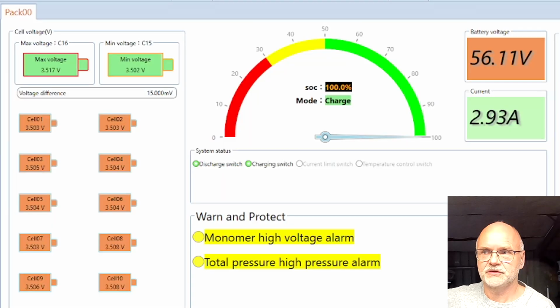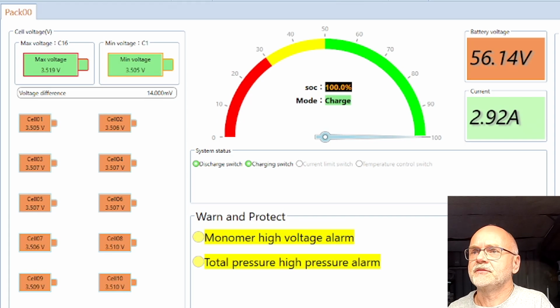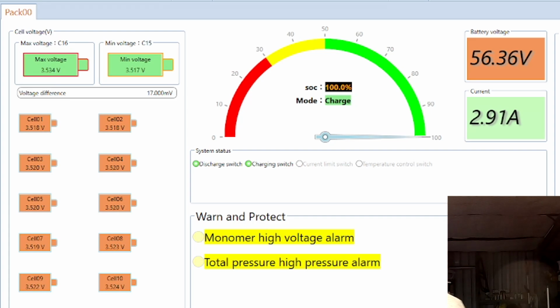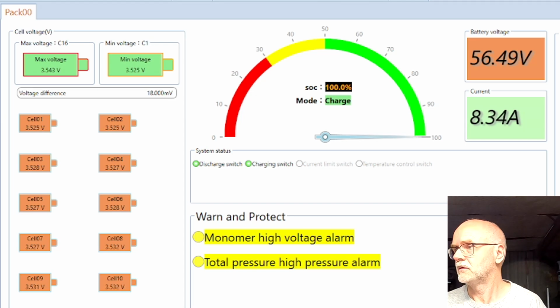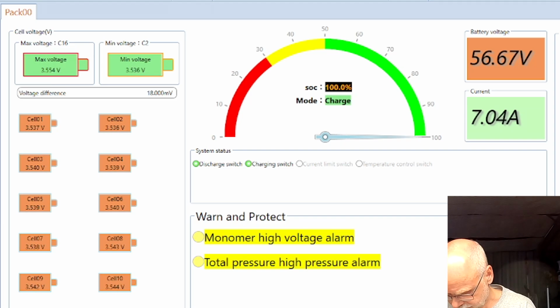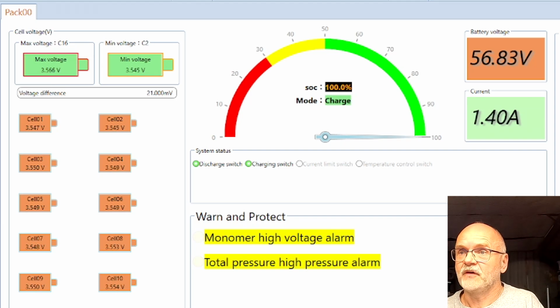I want to increase the voltage now to 56.8, which is 3.55 per cell, and see if we get a higher deviation, to check how well the pack is actually balanced. 3 amps maximum current, we can increase that. Let's see. So this is now 3.55 per cell if everything were balanced, and then the current should go to 0 eventually.